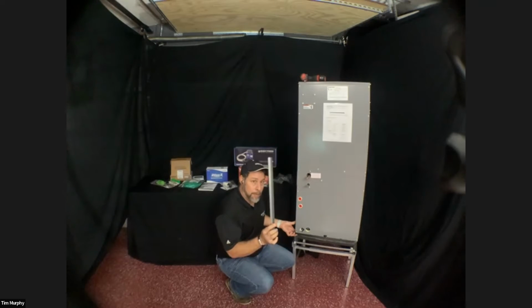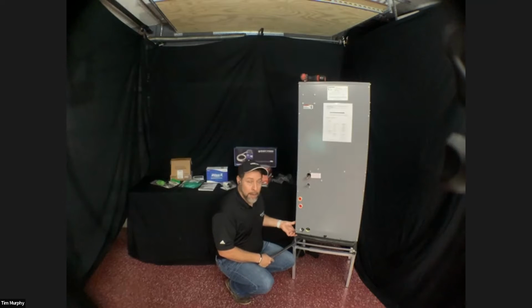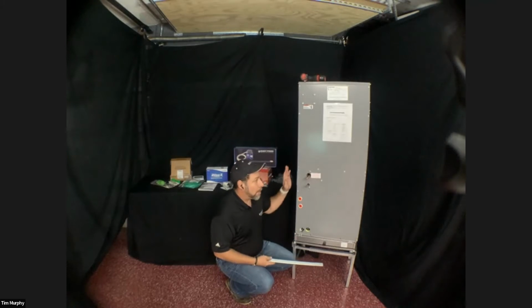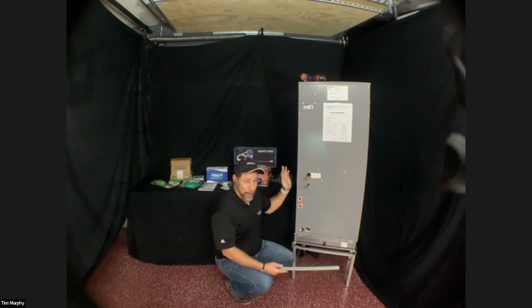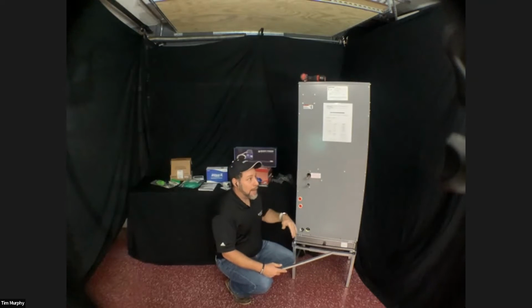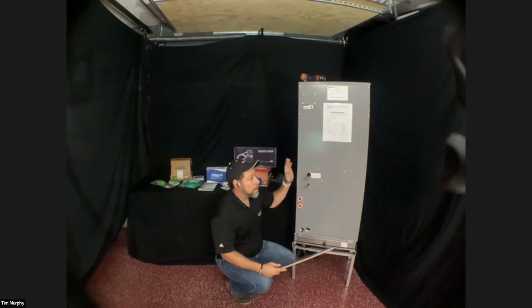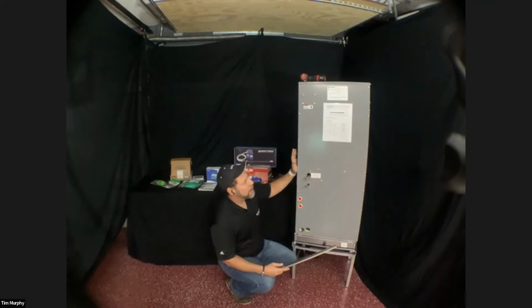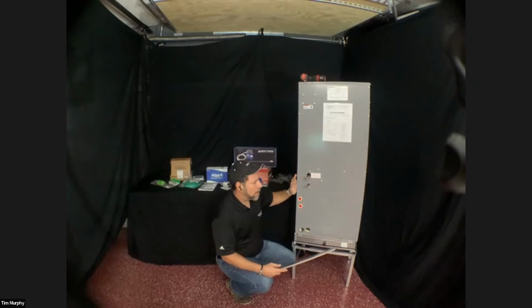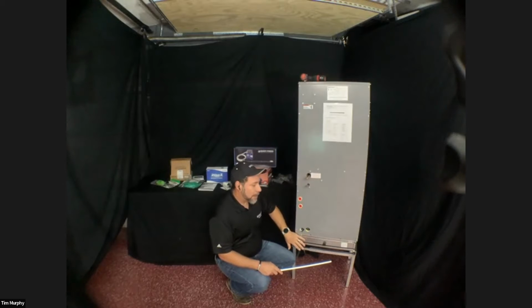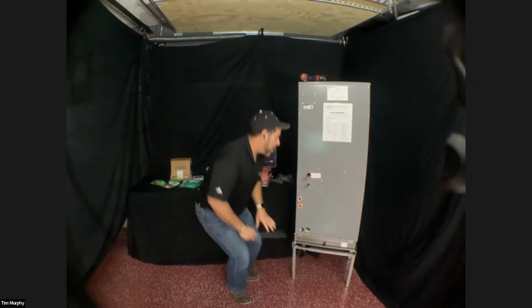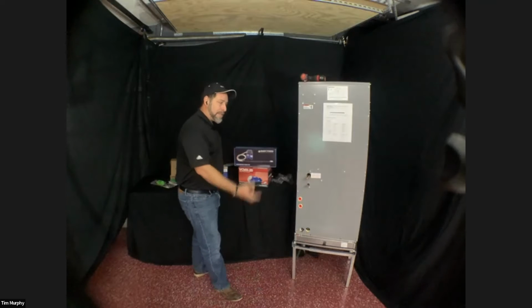You pull these little rails out, and now you can put a 2-inch filter in there. It takes a 20 by 20 by 2-inch filter. The 4-ton cabinet is about 24.5 inches wide, so that's something you want to take into account. It is wider, and I believe it's about 55 inches tall on the 4-ton. This one I believe is 45 or 42 or 44 inches tall, about your average size air handler. But utilizing this 2-inch filter is going to help the performance of your system. It's going to keep your static low.